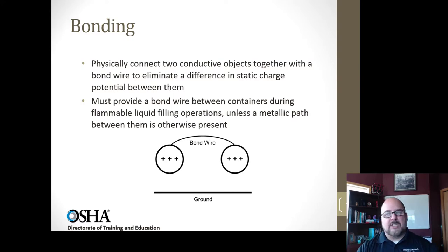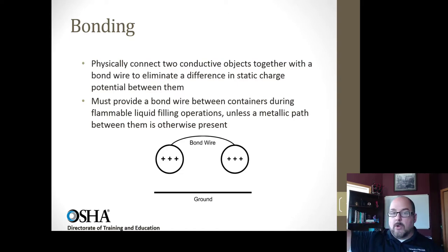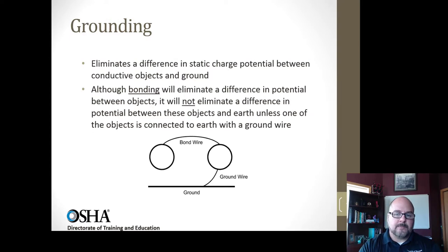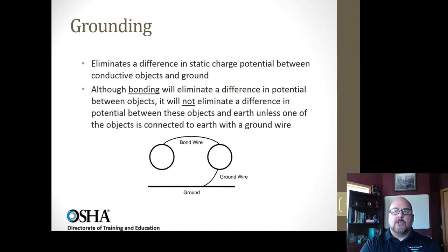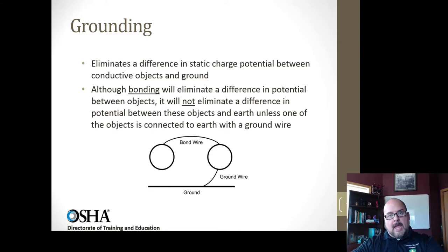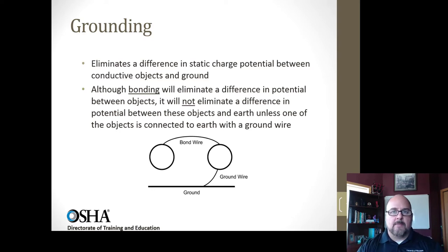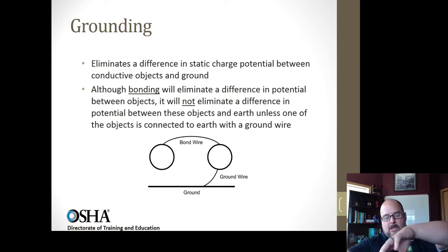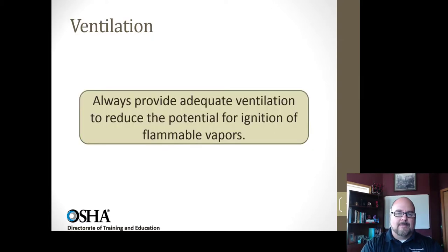In the workplace, we're always required to bond and ground all metal containers, and we should also make sure we don't have any static buildup ourselves. Bonding is basically a metal-to-metal electrical contact between two surfaces. Grounding is an actual line that goes to the ground — the preferred pathway of an electrical charge. In a proper flammable liquid storage room, there should be a line or bar that goes all the way around, dispensing containers should connect to that grounded line, and a separate clamp should bond the receiving container during transfers.